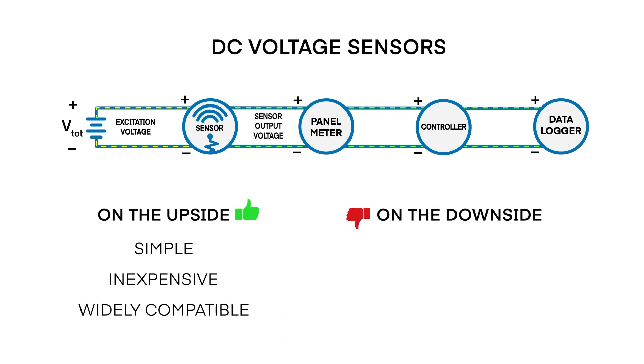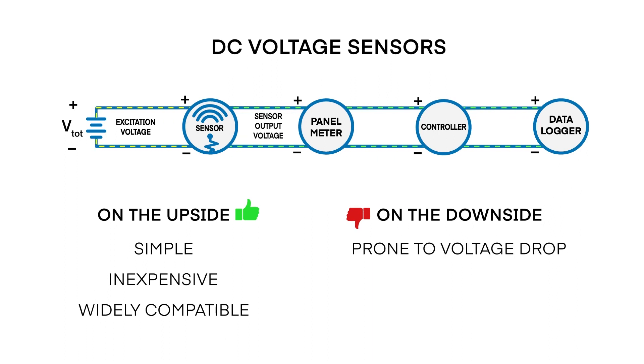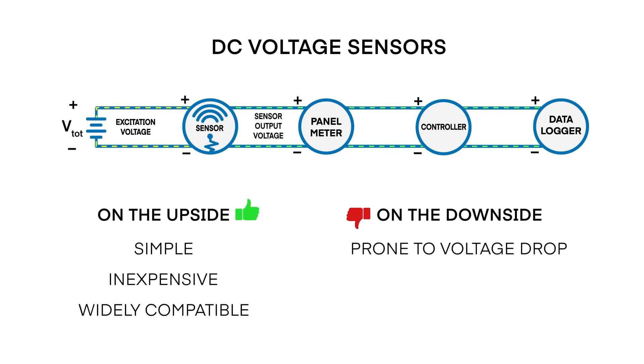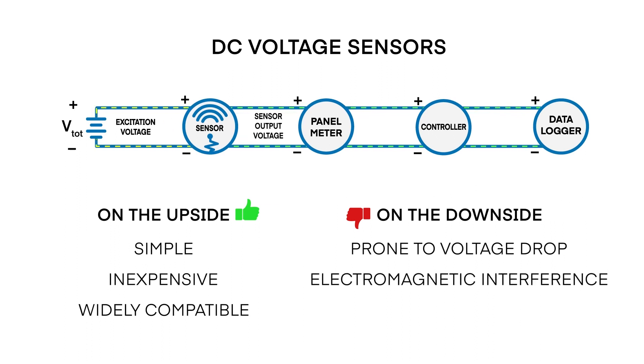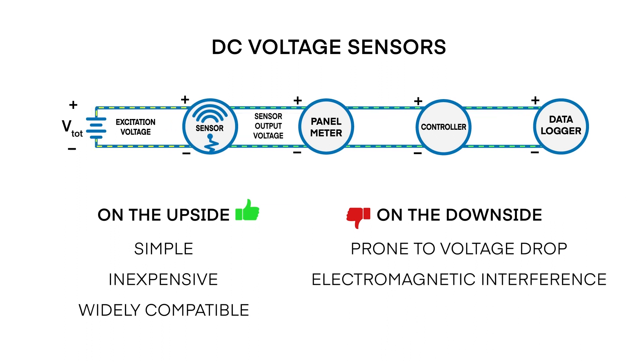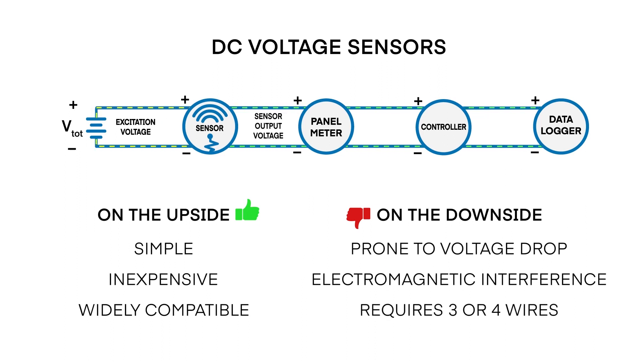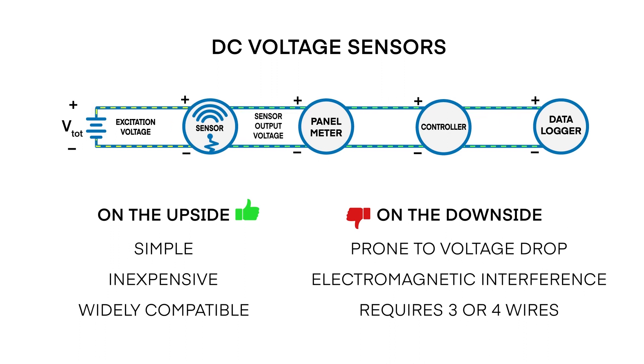On the downside, DC voltage output signals suffer from voltage drop across the length of the cable run, which has a direct effect on accuracy. They are susceptible to electromagnetic noise and interference. And DC voltage output sensors require three or four wires: two for supply or excitation voltage, and two for output voltage.